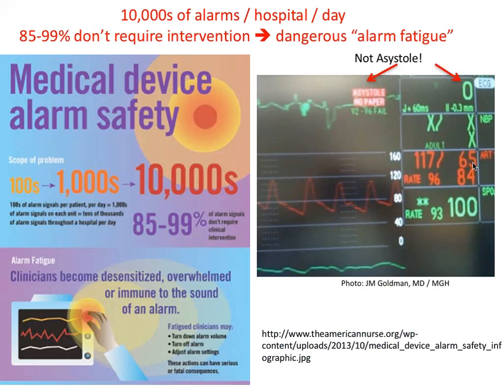The alarm problem is vexing. There are tens of thousands of alarms per hospital per day, up to 99% of which don't require intervention by a nurse, physician, or other person — meaning they're not actionable and they produce alarm fatigue. The screen capture shows an example of a high priority alarm of asystole — cardiac arrest — even though the patient is fine, as you can see from the blood pressure waveform. It isn't that the manufacturer doesn't know how to produce a smarter alarm; it shows the challenge from standards, regulations, and other factors.